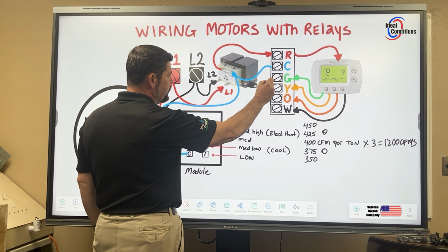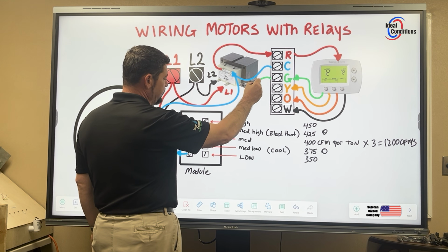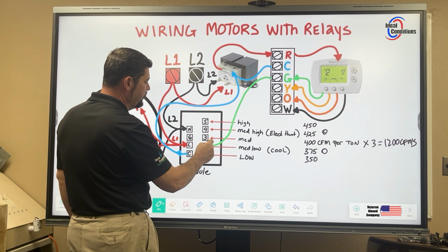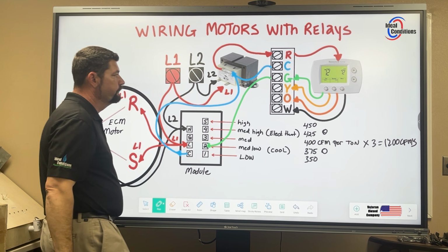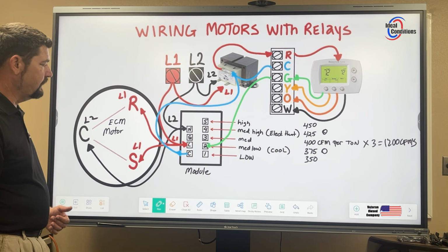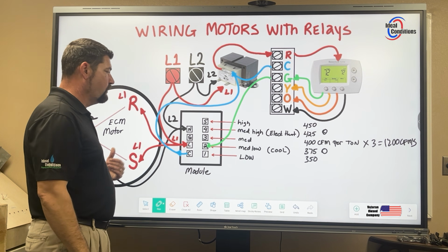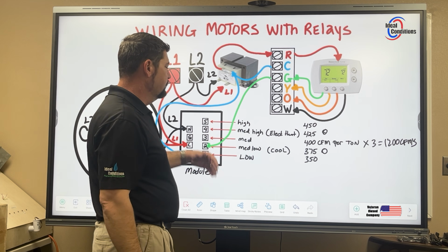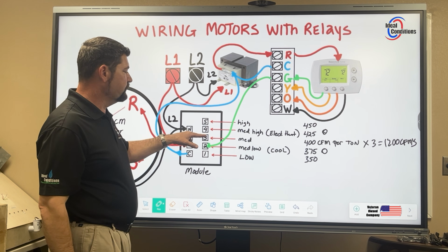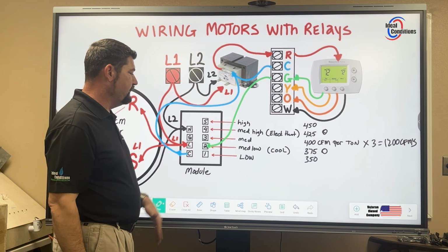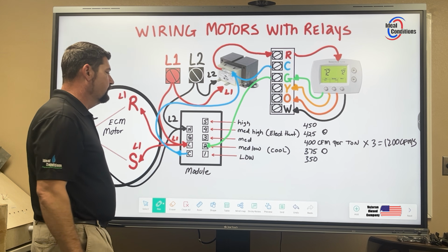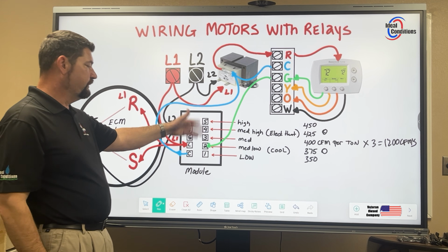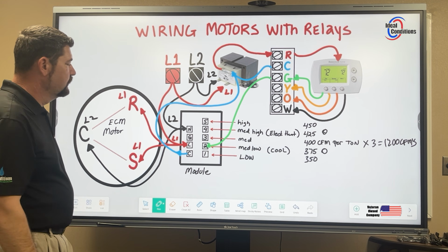They're taking this G call and they're actually running this G call over here to terminal number 2. Okay? And so anytime this motor comes on, it's going to come on and run on medium low. Now you can raise that to another speed tap if you want to run at a higher speed. No problem. Just make sure the power's off, switch your speeds out, you're good to go.